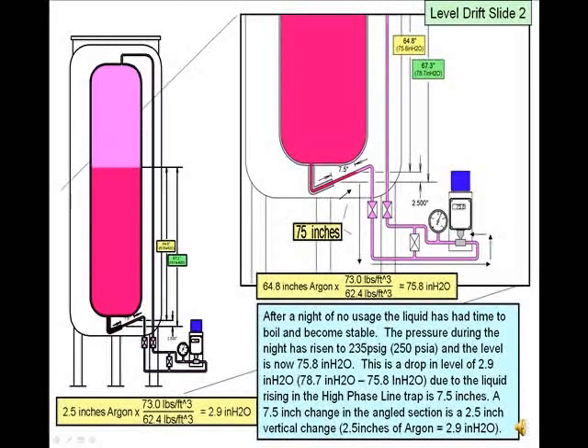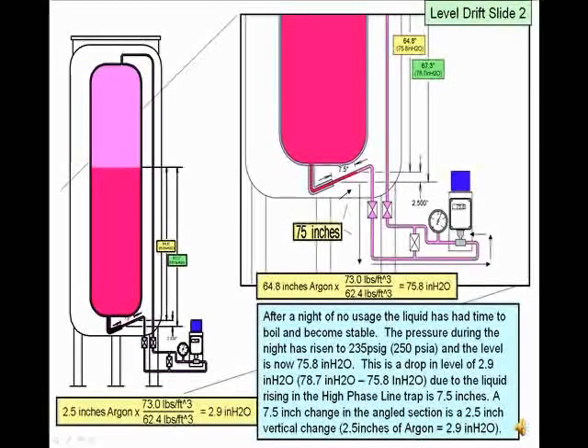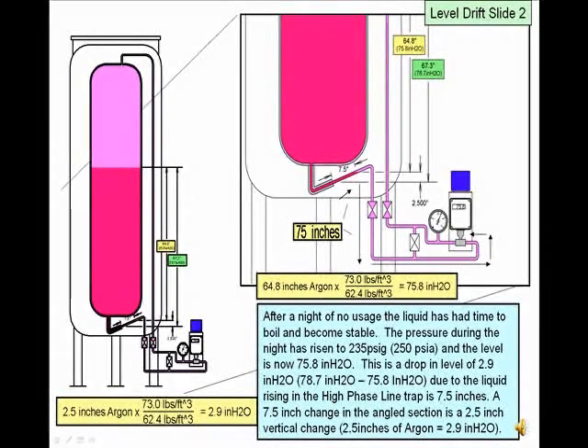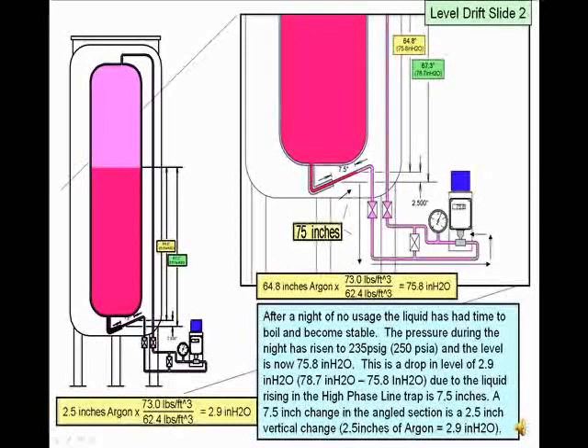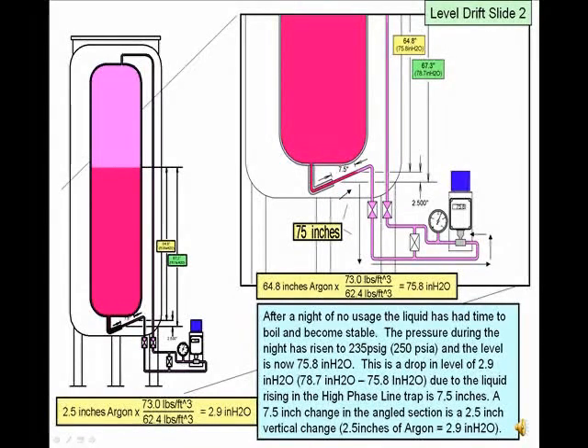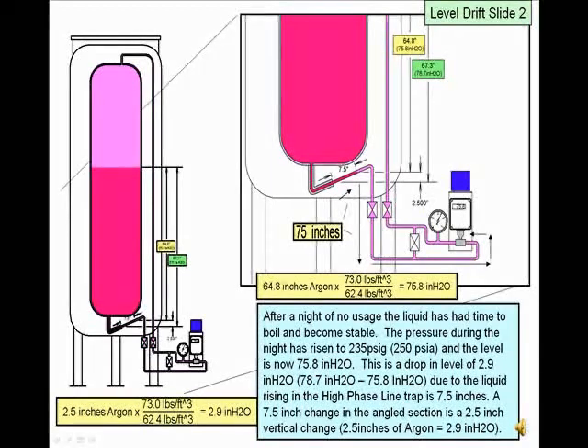As described previously, the tank ended the day in a light boiling mode. During non-usage, the tank's pressure will rise until the liquid has resaturated and the tank pressure has risen to that saturation pressure. In this example, the tank pressure rose to 235 PSI gauge pressure. 210 PSI to 235 PSI is approximately a 10% change in pressure. With a 75-inch gas space above the liquid in the high phase line, ideal gas laws mean the liquid in the trap will move 7.5 inches. The slope of the high phase line results in a 2.5-inch vertical change. 2.5 inches of argon is equal to 2.9 inches of water, resulting in a new gauge reading of 75.8 inches of water.